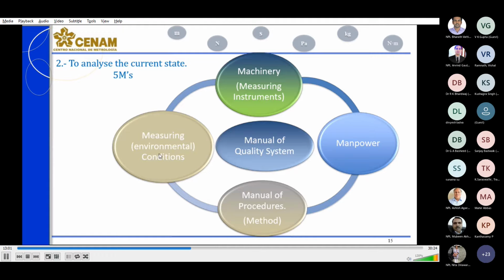Also, the manual of procedures, or all the methods that we use: are they based on written standards, or are they developed by the laboratory? So we have to think about it and know if we have to do some other experiments to be sure that the methods used are strong enough. Also, very important is measuring conditions or environmental conditions, which include temperature, humidity, and also the space, the working tables, the whole area which we use to do measurements and calibrations. And also very important, the manual of quality system. This is the assurance that all we do will be done the same way always, of course, improving each time that we can.